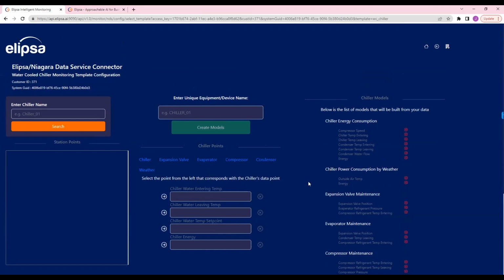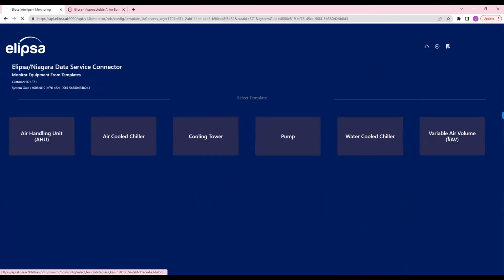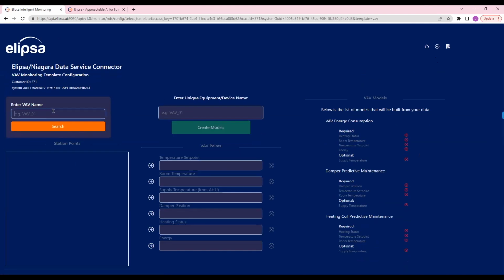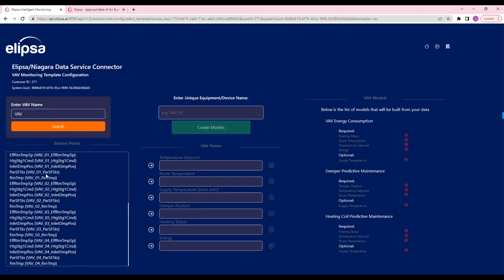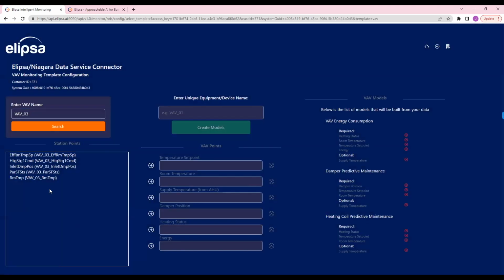In this case, for this Jace, we don't have a chiller, but I'll walk through doing so with another VAV. So similar to how I showed creating the AHU model, if I type in VAV, you'll see all the different VAVs connected that have histories for this particular system GUID. So if I want to build a model for VAV3, that'll filter it down to just VAV3.